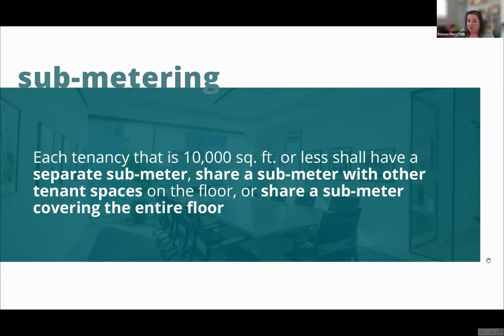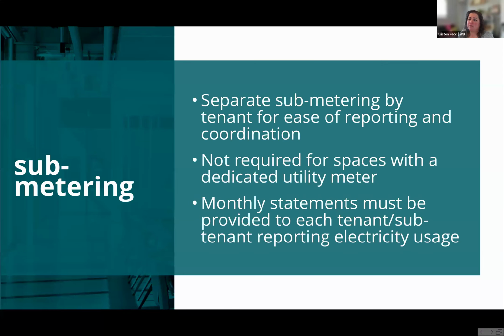It is important to note, though, that while tenant spaces are allowed to share submeters across a single floor, that does often complicate some of the reporting. An owner may choose to provide separate submeters per tenant to avoid complicated calculations to determine usage. If you have a meter for a full floor, tenant A may have 23% of the floor, where tenant B has 57% of the floor, and so on. And you'd have to break down the overall usage per month per space based on their floor area. So that can, for multi-tenant floors specifically, get very complicated. So sometimes owners choose to just take on the onus of installing separate submeters and work with the submetering vendor to apportion that properly.